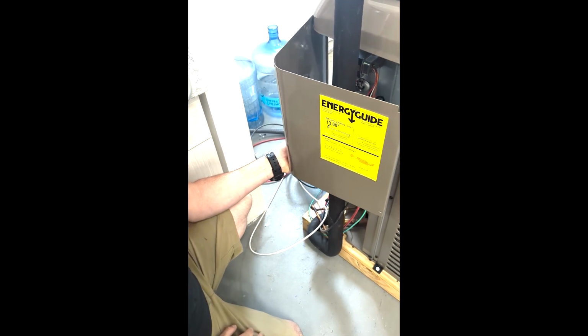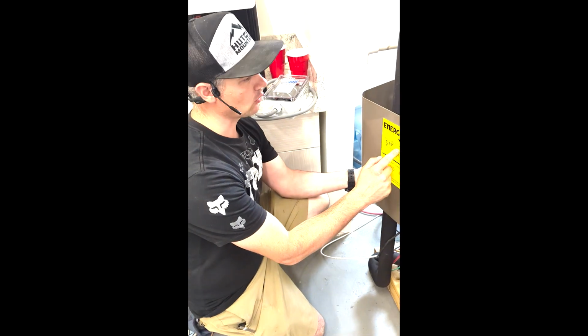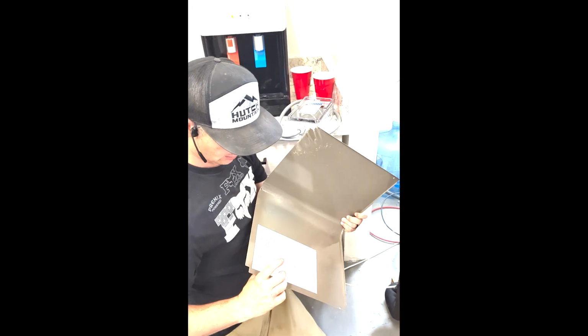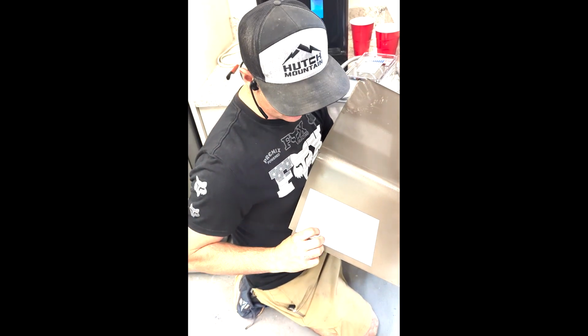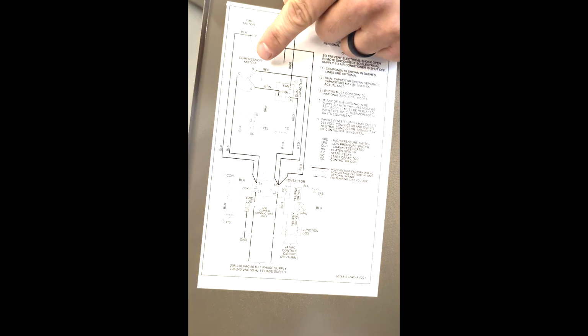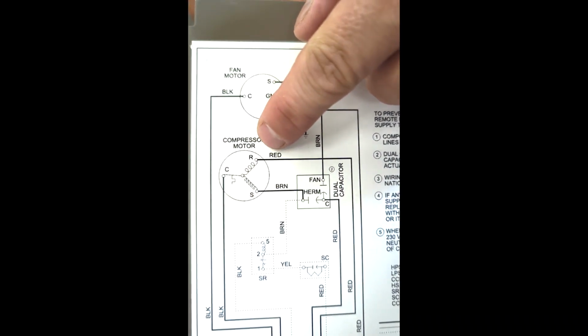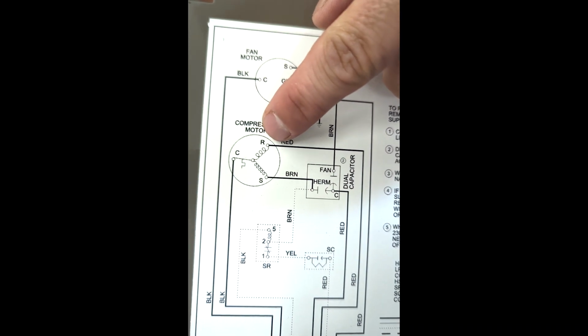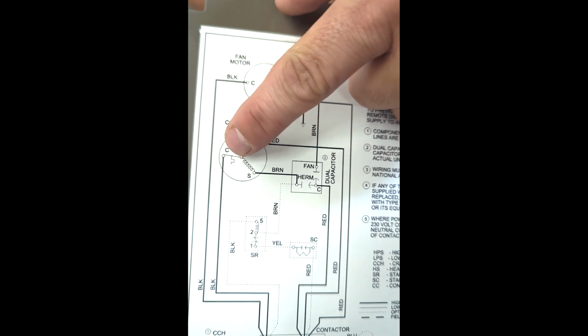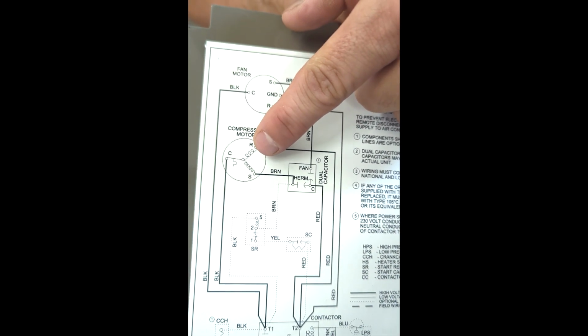Okay. On your air conditioner, when you pull your panel off to access your wiring, there's going to be a wiring diagram usually on the back side of this. To read this wiring diagram, what you want to look for is the compressor. Here, there are three wires that come off the compressor. It's your R, S, and C. These are the three main wires we focus on, okay?